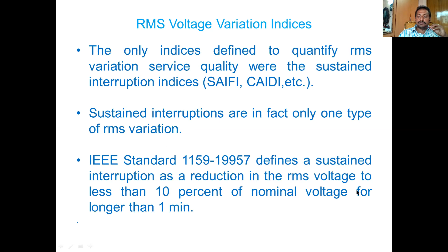IEEE 1159 defines a sustained interruption as a reduction in the RMS voltage to less than 10% of nominal voltage for longer than 1 minute. RMS variations can also be characterized into 3 levels. When you measure these, how can you see them? They can be measured with the help of 3 levels. What are those 3? Number one is phase or component event, number two is measurement event, and number three is aggregate event.